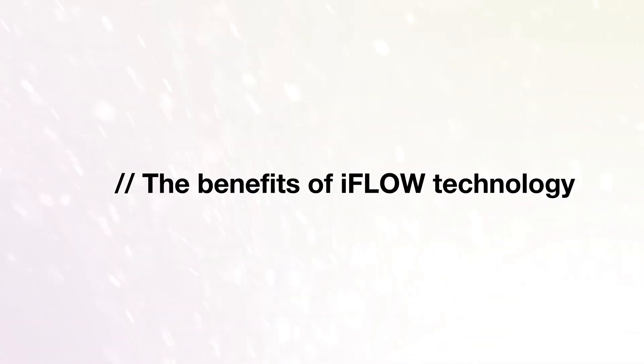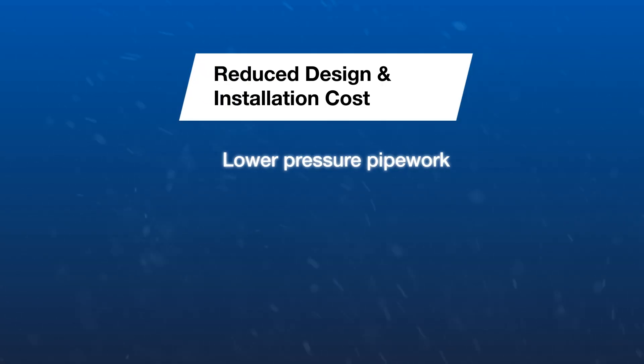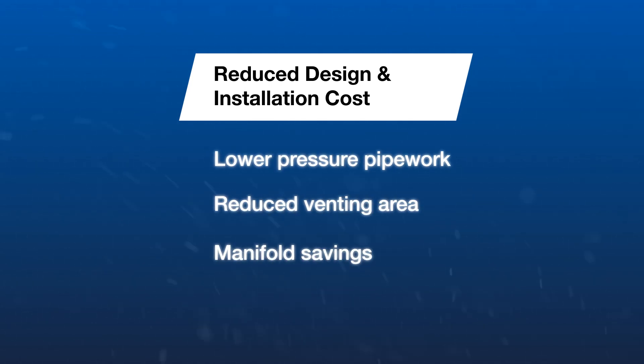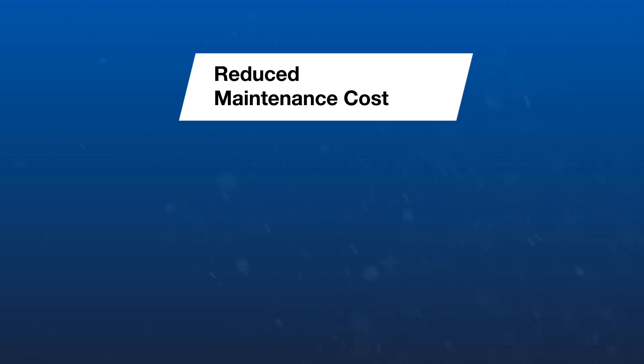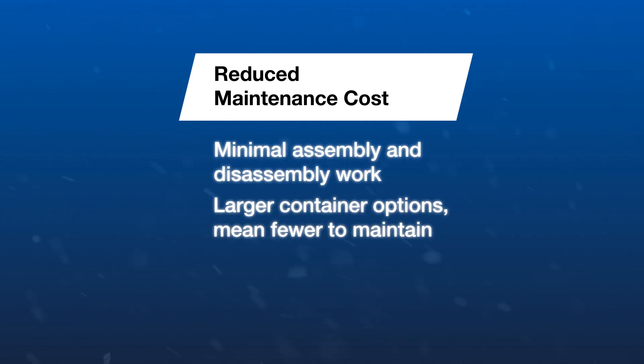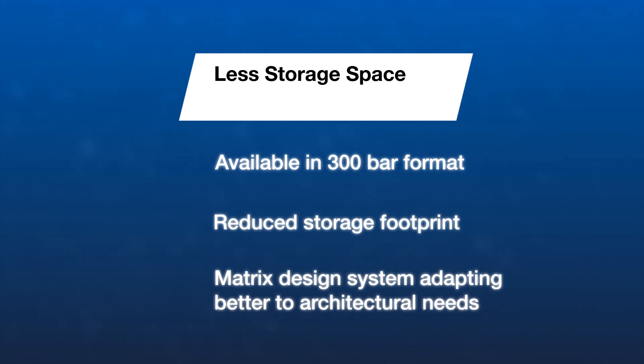Using iFlow technology can lead to a reduction in design and installation costs due to lower pressure pipework, reduced venting area, savings on manifolds, and less installation time. The system aims to reduce the maintenance cost through ease of assembly and the option to use a lower quantity of larger containers. The Ansul iFlow system is available in a 300 bar format, lowering the storage footprint, and is adaptable to make the most of the available space.